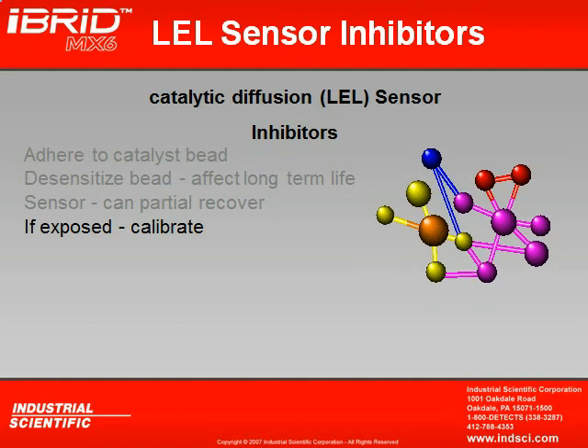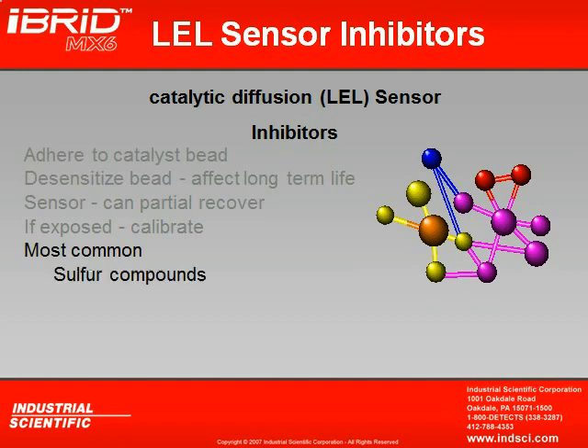Now, the most common inhibitors we have to be concerned with are sulfur compounds. A lot of people get concerned about sulfur compounds because whenever they calibrate their H2S sensor, they're exposing their combustible sensor to hydrogen sulfide. And they'll say to me, Brad, does that mean every time I calibrate my instrument to hydrogen sulfide that I'm going to damage the combustible sensor? And the answer is no. When we're talking about sulfur compounds, we're talking about very high levels of sulfur compounds, levels that are dangerous to human life. Not the low concentrations you find in your calibration gas cylinder or day-to-day exposures.